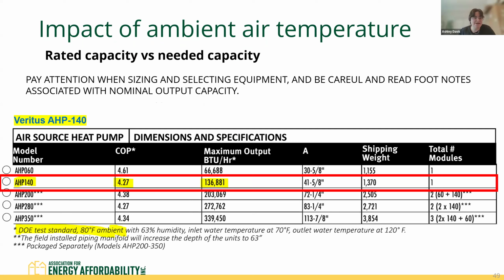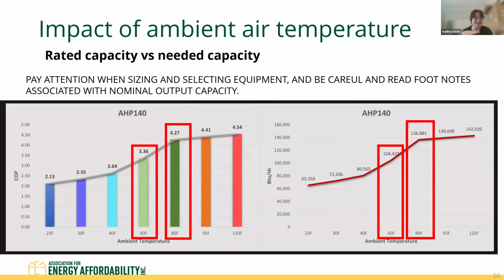And then you also have to think about ambient air temperature and your rated capacity versus how the unit performs at lower temperatures. So this is an example of Lochinvar's heat pump water heater, and you can see that the unit may have this maximum output capacity. Next slide. But that capacity and the COP start to drop pretty significantly as the ambient air temperature drops. So you have to look at your design temperature depending on where your property is located and make sure that you're still going to have enough heat pump to cover the load on those colder design days. Next slide.